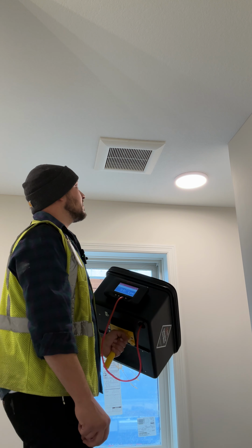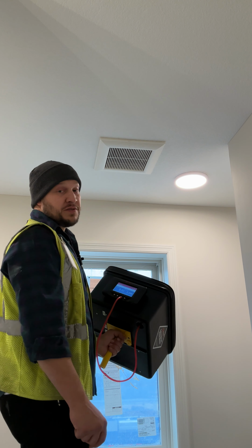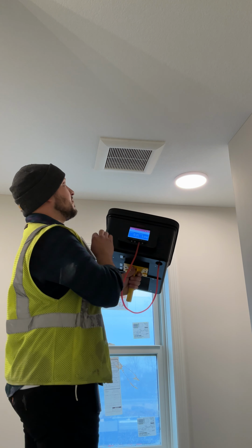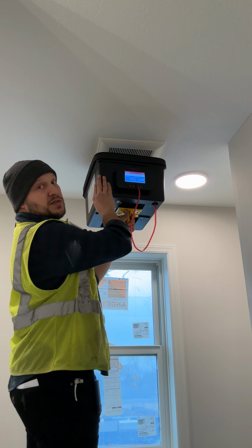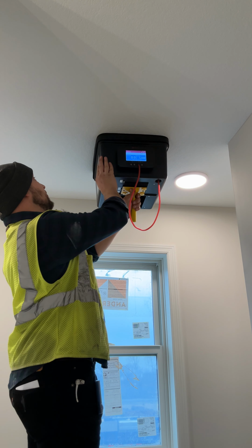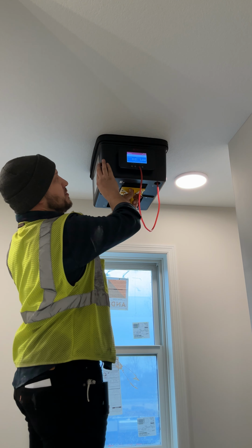Here we've got an exhaust fan, spot ventilation for a bathroom, and we're going to confirm that we're meeting at least 50 CFM flow that we're looking for. So we'll use an exhaust measuring device here. It's a box that will measure the pressure and tell us we're hitting about 71, 72 CFM here. So that confirms that we're moving enough air.